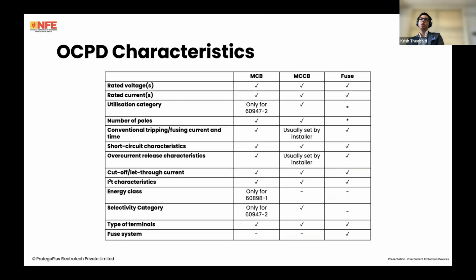Now, when it comes to the characteristics of different overcurrent protective devices, I have broken it down. I give you three columns here: MCBs, MCCBs, and fuses. You look at the rated voltage, these obviously apply for all three. Rated currents obviously apply for all three. We've got utilization categories. We'll get into what they are. These are only really given for MCBs to 60947 Part 2 and for MCCBs. And for the fuse, it's given for the switch fuse disconnector. Number of poles is obviously applicable for both MCBs and MCCBs. And then again, for the fuse, it's only applicable to the switch fuse disconnector.